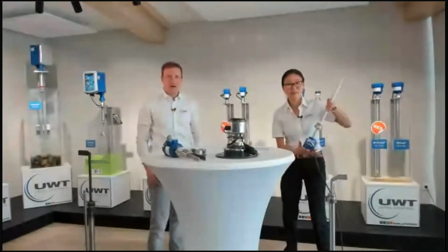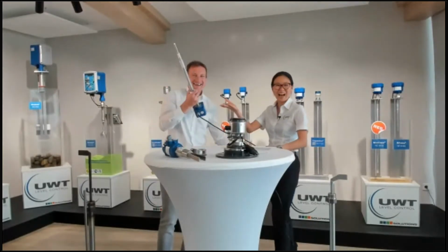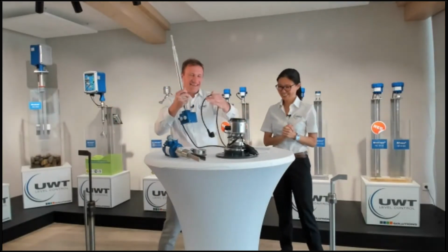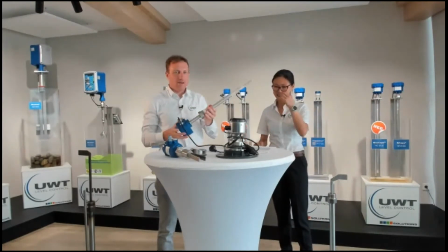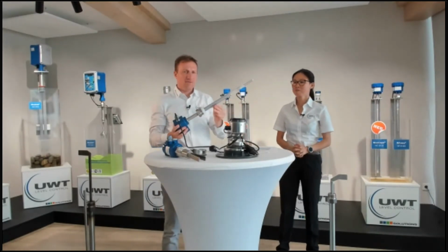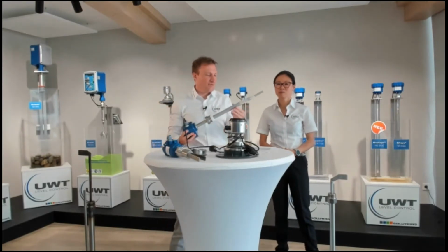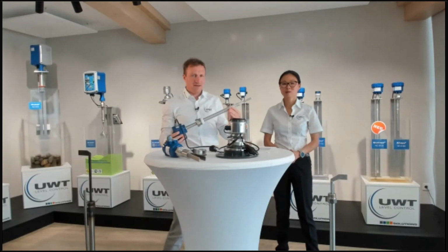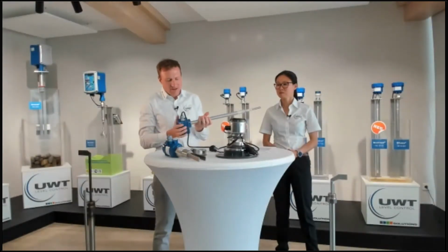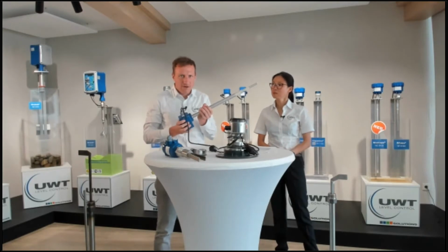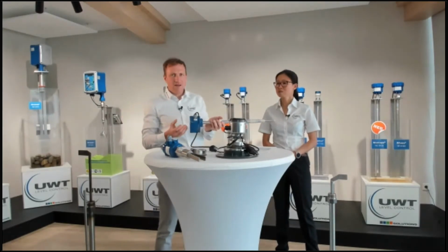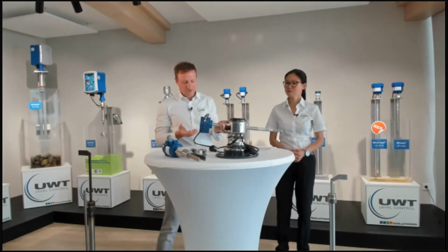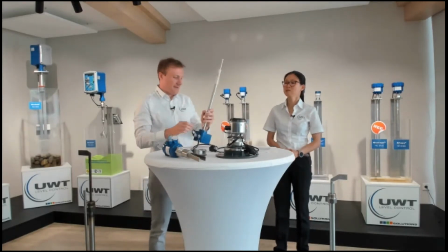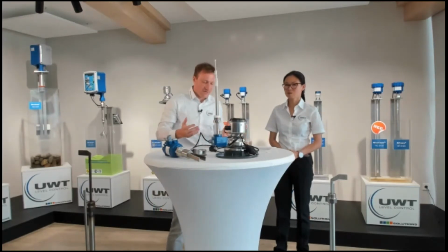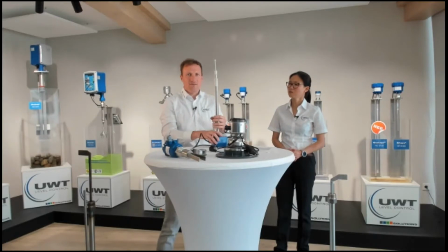Can you give us a little bit more details? Yeah, this time we use the RF Nivo, with the capacitive principle. Here we have this special design with a PFA coating around the probe. Normally the probe is made out of stainless steel with some PEEK insulations. Special here, also with the standard version, we have the automatic calibration and also a display where we can see the measured capacity. Just one click on a button, and the sensor automatically calibrates on its own to the specific application conditions.